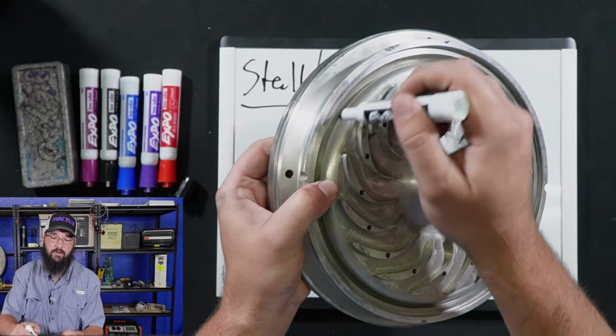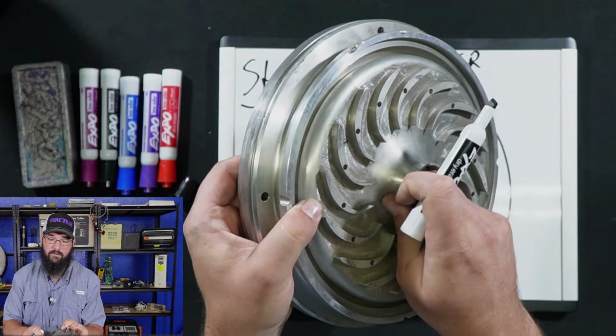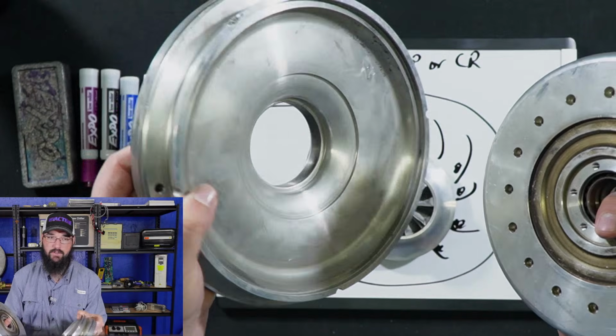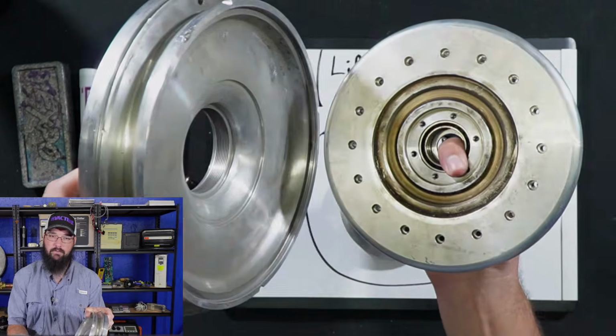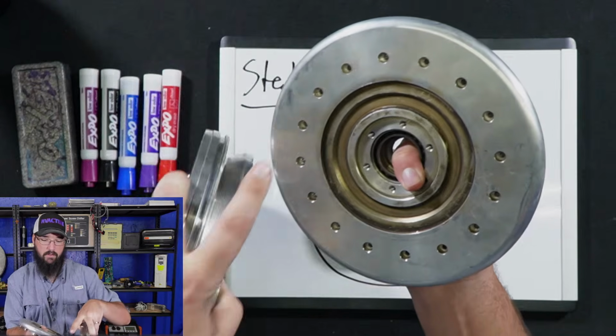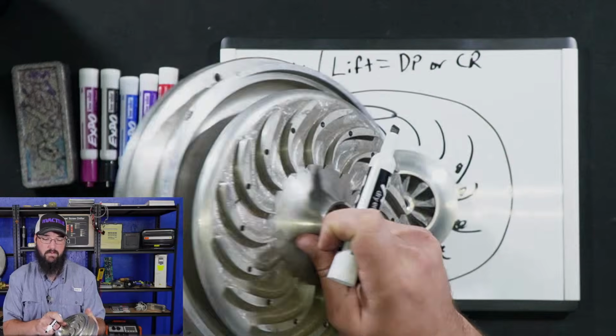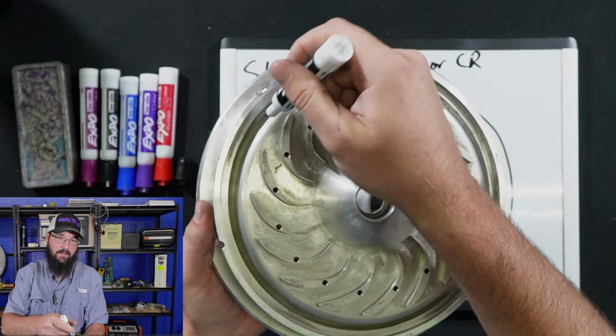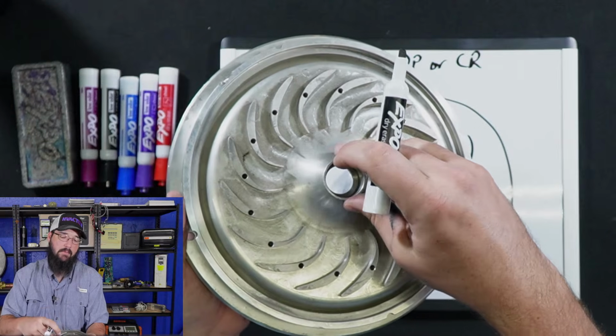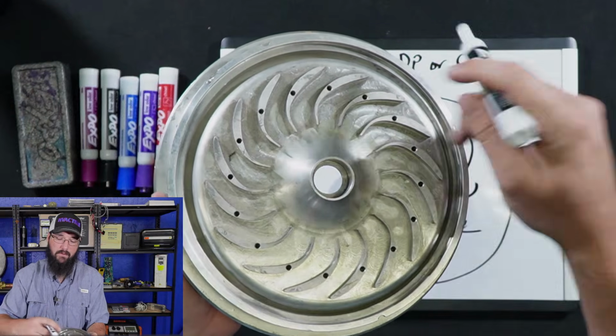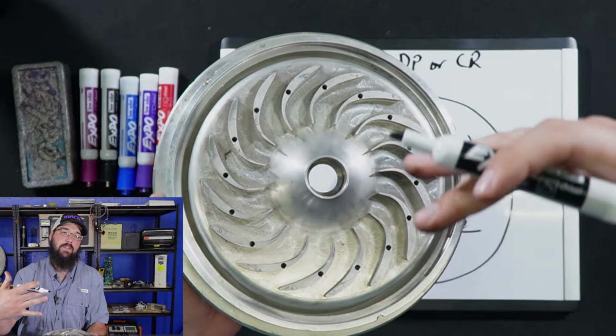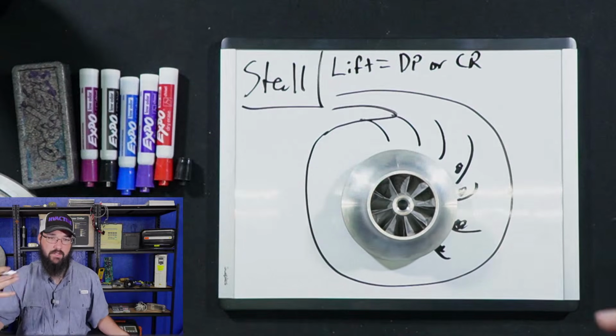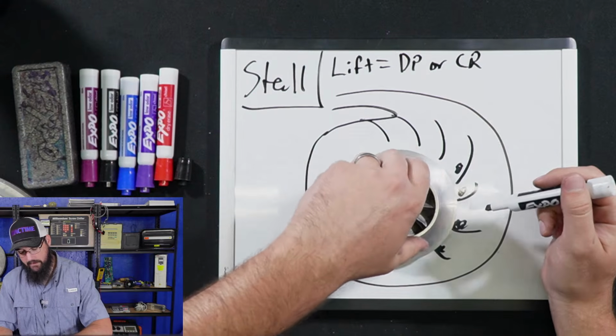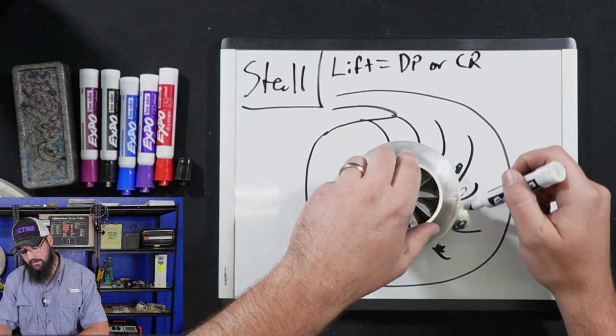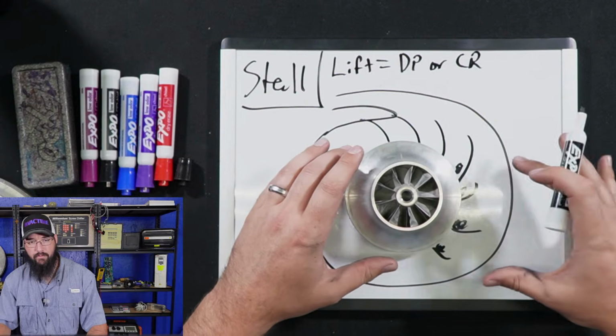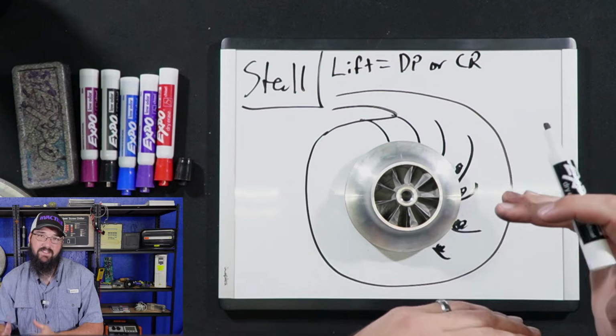So this is your discharge coming out of this first stage impeller on this compressor. This right here is your suction side coming in. This is the backside of your diffuser assembly. So all of this is part of your diffuser. And then it comes out in this little gap right here. Now this is feeding into another impeller, but this gap is what would feed into the volute or the discharge pipe that leaves the impeller. So as this is spinning, this section right here is no longer able to move the refrigerant. It literally stalls or gets stuck in its position.